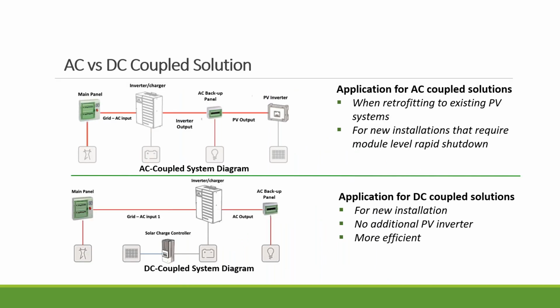Okay, we're going to talk about how you integrate the battery with your PV systems. There are two different ways of doing that. One is called AC coupled systems. I'm sure a lot of you, if you're based in the United States, are very familiar with that. Basically, you already have PV inverters, existing PV inverters. It could be string inverters, it could be microinverters, it could also be a SolarEdge inverter, right? Optimizer plus string inverter. And then you just hook up your energy storage to the existing inverters.